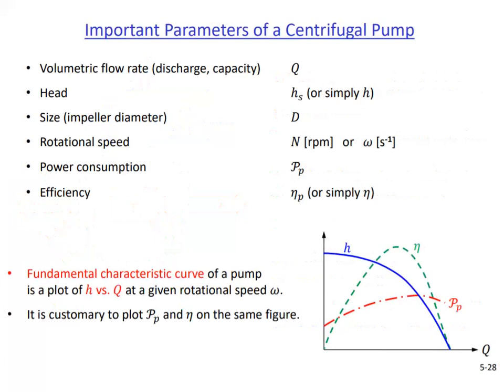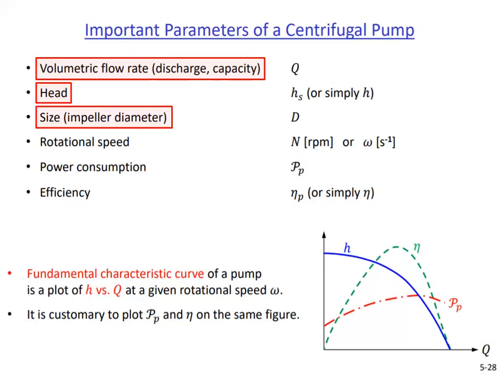Here are the most important parameters related to the design and operation of a pump. First one is the flow rate, which is also called discharge or capacity. Next one is the pump head. Size of a centrifugal pump is defined by the diameter of its impeller disc. Rotational speed is also important because a pump's H-Q relation changes as the rotational speed changes. Last two items are the power consumed by the pump and the efficiency.